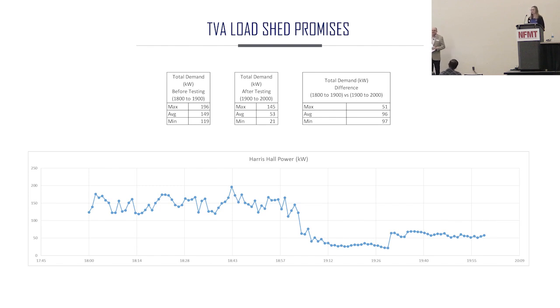So, as you do load sheds, you can do resets, static pressure resets, discharge air temperature resets, instead of just trying to shut equipment off, because then that equipment has to come back on at some point. And so changing set points can help you reduce that demand, or reduce the load, instead of just shutting equipment off.